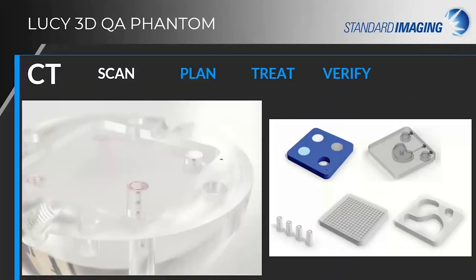So along the end-to-end QA, we're talking about scan, plan, treat, and verify. Lucy is put through the same processes as your actual patient, which means, again, that the Phantom will be scanned on CT and/or MRI to start that treatment chain.